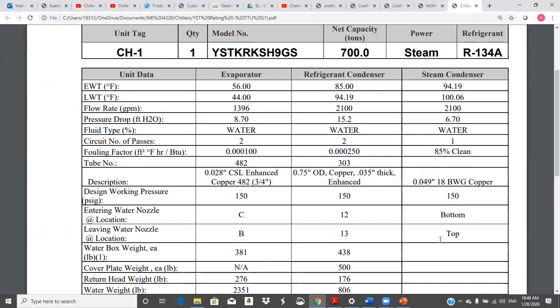We were looking at this with a couple other locations. And I said, well, just send me a spec sheet. I just want to see what this thing looks like. So you can look at some of the numbers. R134A, that's a typical refrigerant for a centrifugal chiller. This is 700 tons capacity. Entering water temperature, 56. Leaving water temperature, 44. Got a 12-degree delta T across the chiller. All pretty standard stuff.